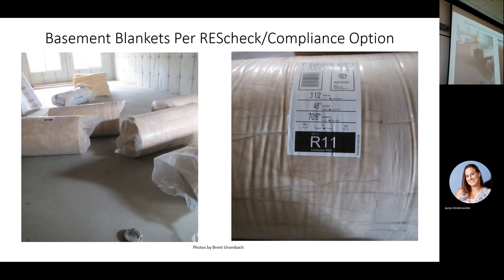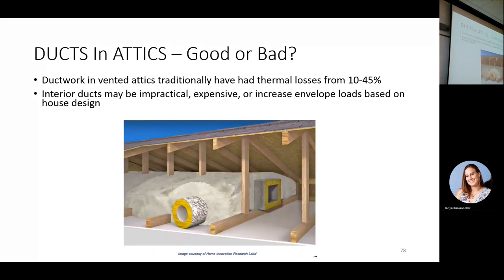Basement blankets per the REScheck or whatever compliance option you use. And ducts in attics, and we've already talked about this quite a bit, so we'll move through pretty quick. But I have seen some of them. DOE says that we have 10 to 45% thermal losses because we put ducts in attics. In our hot climates where we get a lot of sun and our attics get hot, it's more at the upper end of that, and it stays. Sometimes it's even worse. I've seen them at 50% of the load. It's to overcome that load. So burying it in the insulation really helps. If we can get it inside the envelope, it's even better.